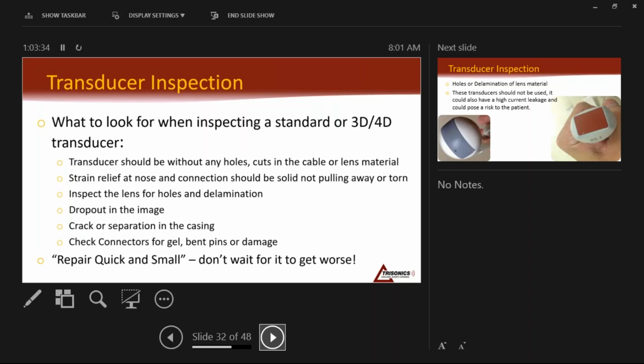So, transducers should be without any holes or cuts in the cable or lens material. The strain relief at the nose and the connection should be solid and not pulling away or torn. Bad strain reliefs are a huge issue with probes dying. Once that strain relief goes, we see people tape them, glue them, use them for another 4 or 5 days. If you use a probe with a bad strain relief for 4 or 5 days, the probe's dead, unless we can replace the array. It's going to pull the wires out of the array, and it's going to be gone. Inspect the lens for holes or delamination. Obviously, if there's dropout in the image, the probe needs to be evaluated. Also look for any crack or separation in the casing.